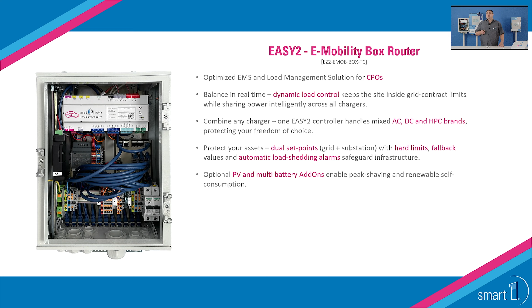It has a dual set point functionality, so you can limit the grid, you can limit the substations as well if you have the requirement for this. You have hard limits and fallbacks, so in case the meter is failing, in case you have a hardware failure, we have the functionality to do automatic load shedding alarms to safeguard the infrastructure. So if, for example, the meter fails, you can define a fallback scenario with a fallback power that is always provided. But we can also add things like PV. You can add multiple batteries for functionalities like peak shaving or supporting the charging infrastructure with an additional battery. You can have self-consumption optimization if you have this requirement.